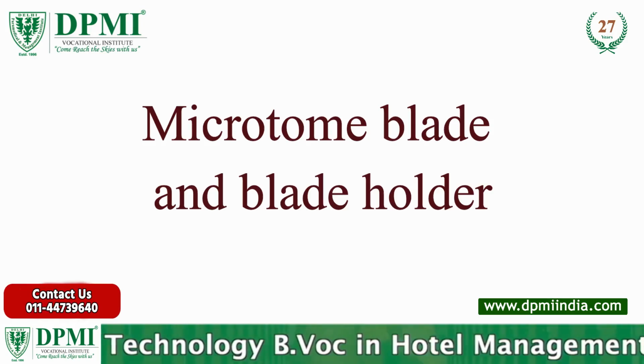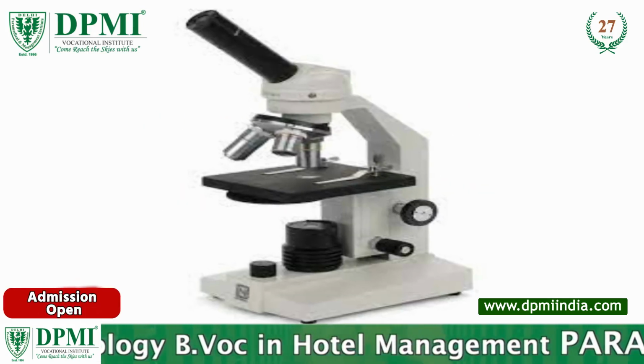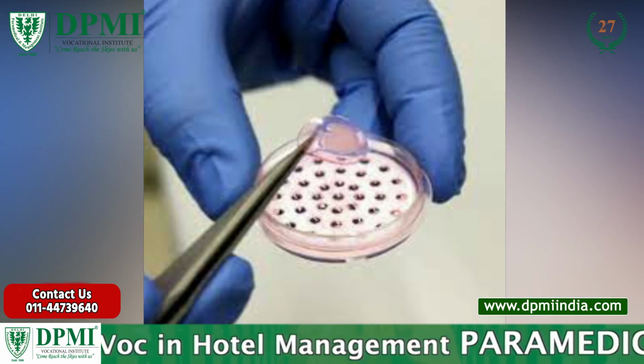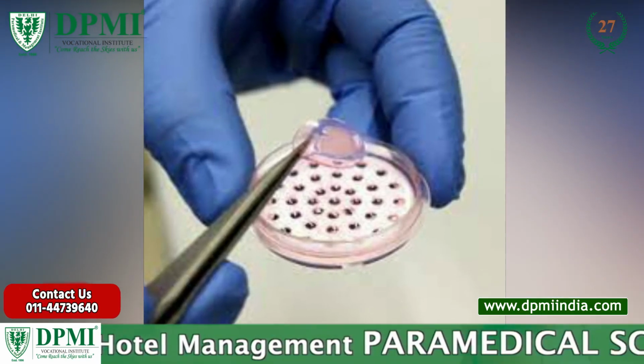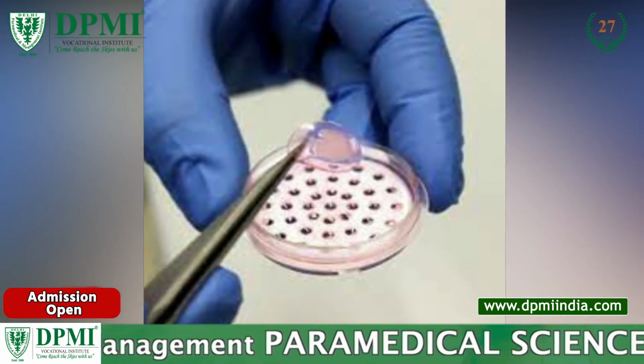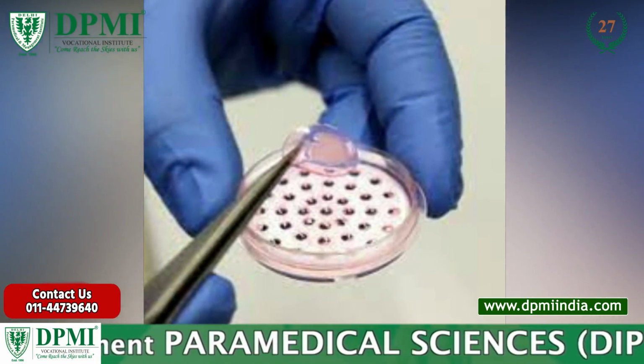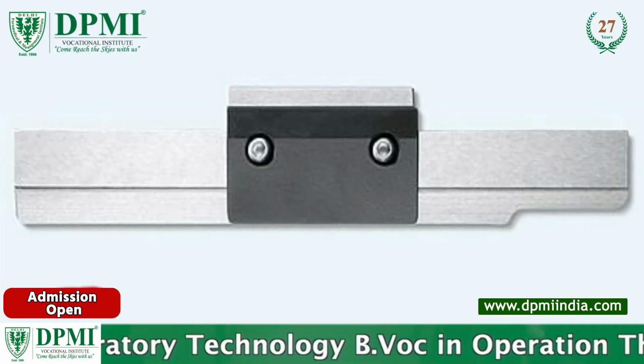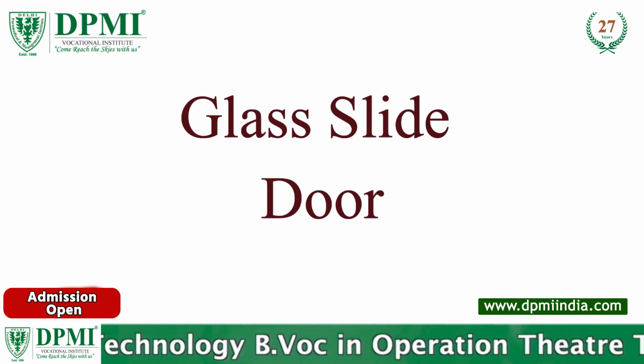Microtome blade and blade holder: in order to observe tissue under microscopes, it needs to be sliced to an appropriate width, on the order of a few microns, which requires precision cutting with very sharp blades. Glass slide door: this is basically a cover for the cryostat.